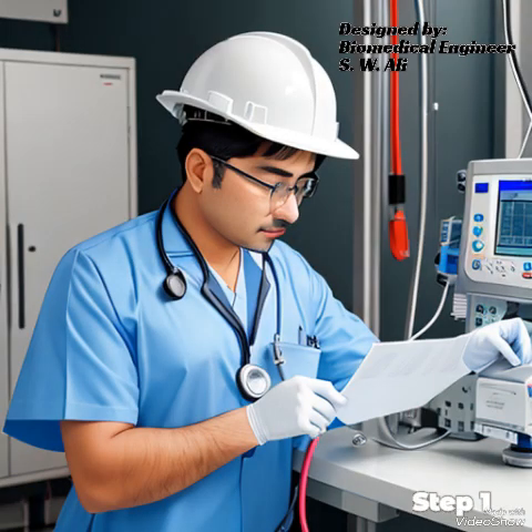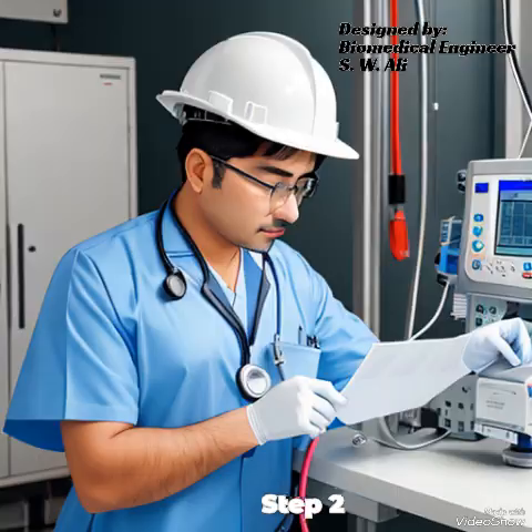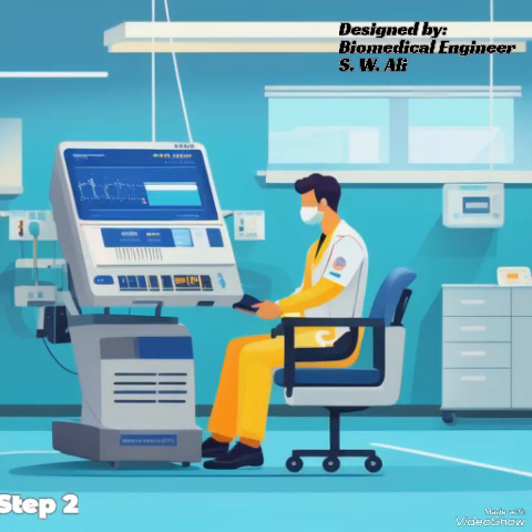Step 1: Complaint documentation. Record the complaint or issue reported by the end user, including details such as symptoms, error messages, and any recent incidents. Step 2: Initial assessment. Review the equipment's service history and perform a preliminary assessment to identify potential causes of the issue.